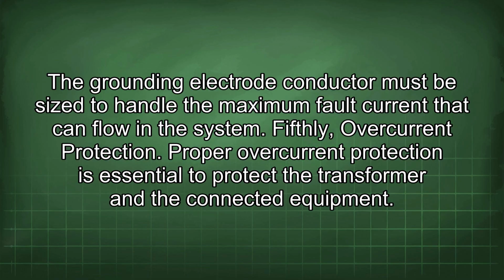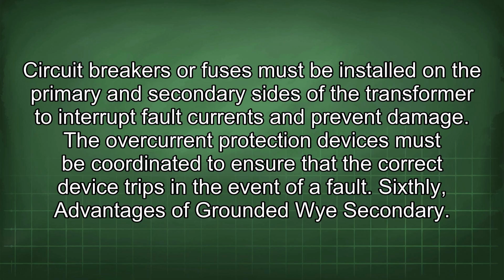Fifthly, overcurrent protection. Proper overcurrent protection is essential to protect the transformer and the connected equipment. Circuit breakers or fuses must be installed on the primary and secondary sides of the transformer to interrupt fault currents and prevent damage. The overcurrent protection devices must be coordinated to ensure that the correct device trips in the event of a fault.